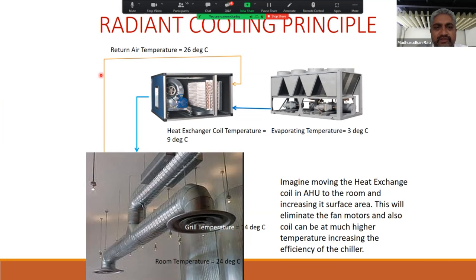Okay. So how that is today, you are distributing the cooling by having the heat exchange in this dense heat exchanger. But imagine if I were to take this heat exchanger out of that AHU in the AHU room and put it on the ceiling in each of the areas which you are cooling, then what happens? Then you don't need the ducting, you don't need the fan, and you are not constrained by the time that it takes for that heat exchange. So you will have more surface area.